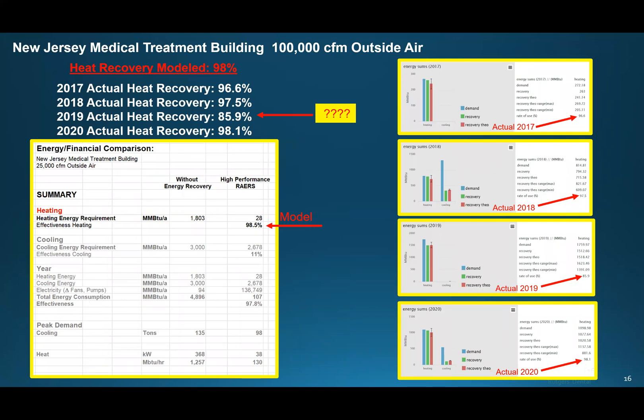And one last example — a medical treatment building in New Jersey with 100,000 CFM of outside air. The model calculated 98.5% annual heating effectiveness. Actual post-occupancy results: 2017 — 96.6%, 2018 — 97.5%, 2019 — 85.9%, and 2020 — 98.1%. In 2019 performance dropped about 10%. The archived monitoring data shows that in 2019 the supply air temperature was increased from 55 to 65 degrees, then set back to 55 in 2020 — explaining the decrease. The model was run at a supply air temperature of 55 degrees.